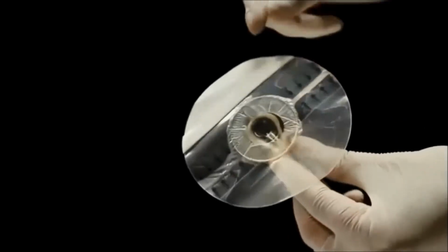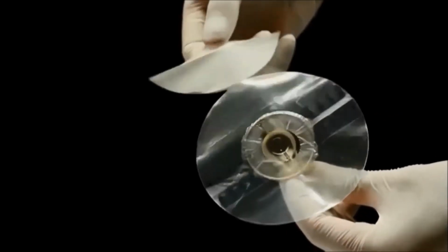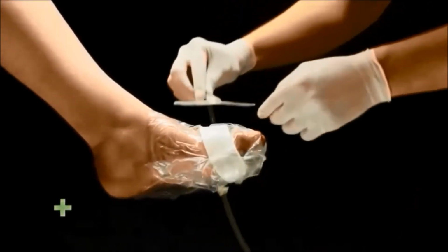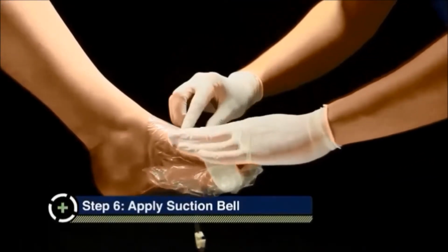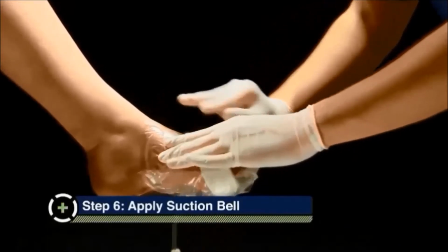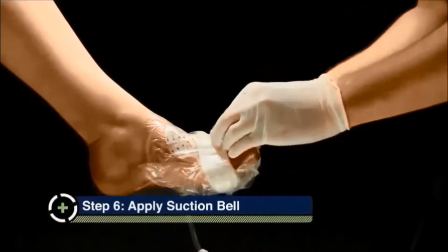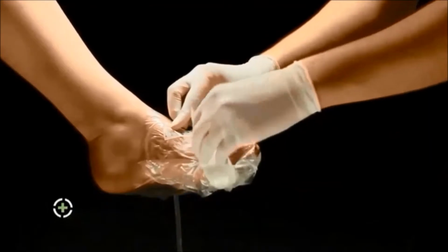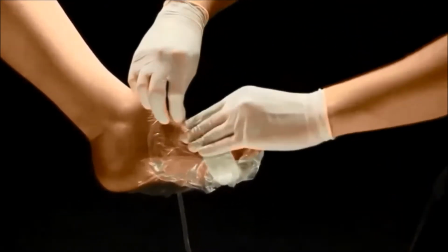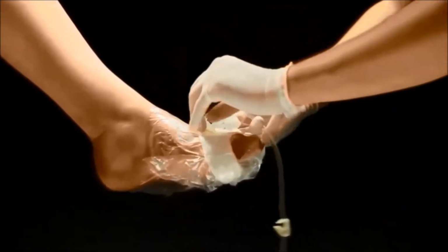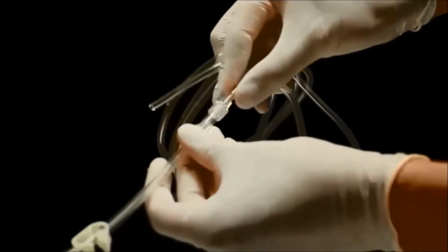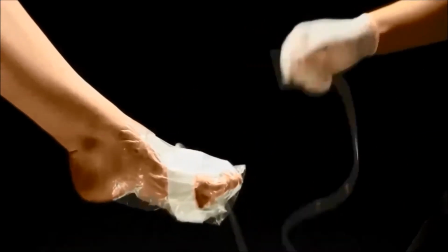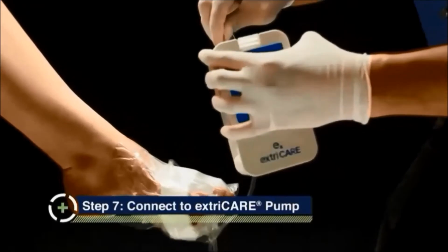Remove the suction bell from the packaging and remove the backing layers. Place the suction bell opening directly over the hole in the drape with the tubing at the desired angle. Remove the top portion of the backing layer from the suction bell skirt. Attach the connector tubing to the suction bell. Connect the tubing to the extriCARE NPWT pump.